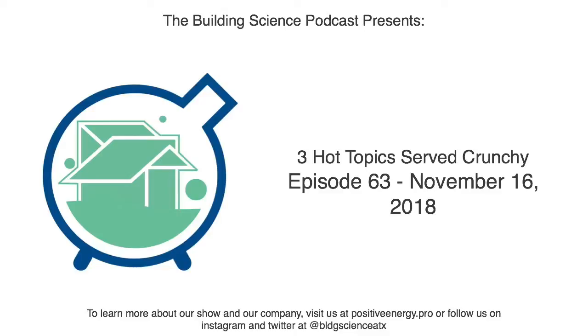So what's your, don't tell us your trade secret, John, but there's three big moves. Now there's smaller moves, but the three big moves are: slow the air down by using a little bit bigger ducts than our typical practice. Bigger ducts, your air is moving more slowly, you have less turbulence going around the fittings. Two is don't use flex duct for making turns. Use smooth sheet metal, so sheet metal elbows, smooth inside corners on any rectangular elbows and things like that. So both of those, that's really easy.